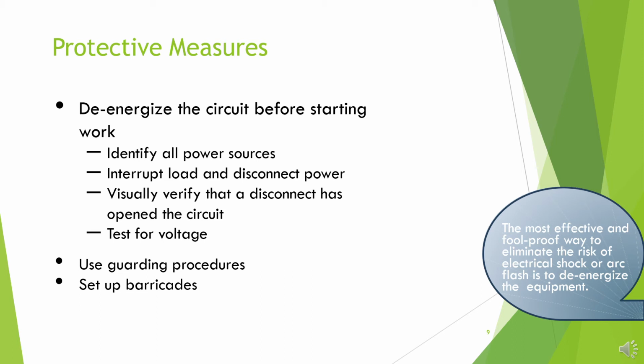Next, when disconnecting the power, ensure the load has been taken off. You never want to disconnect power when there's any load on the circuit. If possible, though it isn't always probable in our line of work, visually verify that something has been disconnected or a circuit opened, which is a great verification method. And finally, test for voltage.